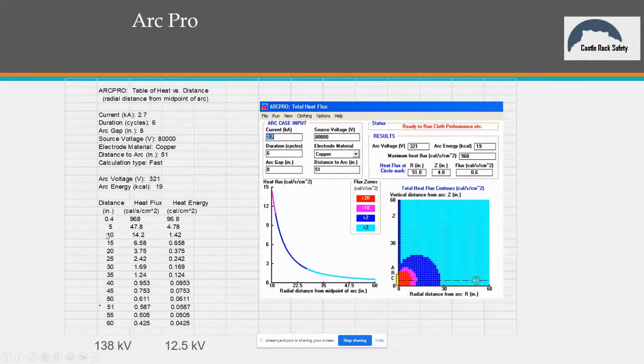So it's going to be here between 10 and 5 inches. So probably about 7 inches, somewhere in there. And I can play around with it and get the exact number, but that's where my 2-calorie boundary is. So think about this, guys. My 2-calorie boundary on 138 kV, let's just say it's 10 inches, right? That's where my 2-calorie boundary is on 138 kV based on the fault current that I used here, which is an actual scenario that I calculated for one of my clients.